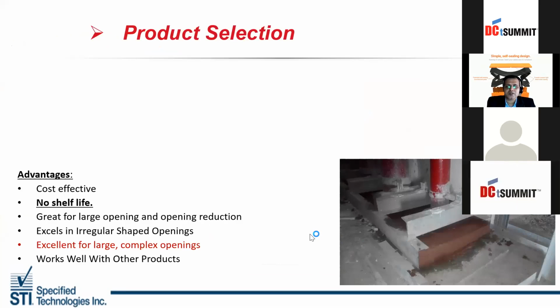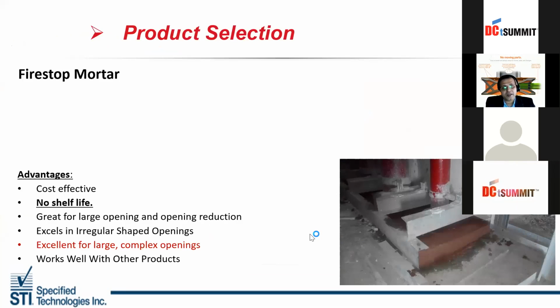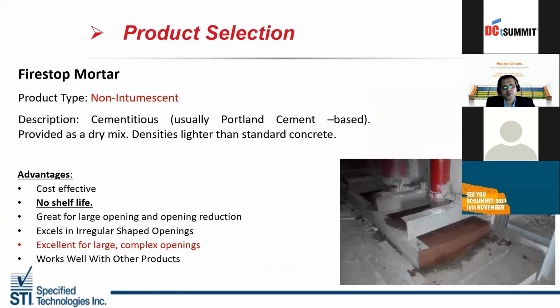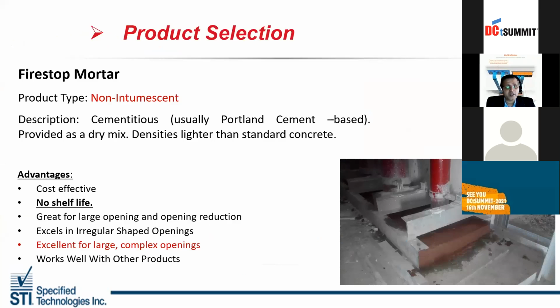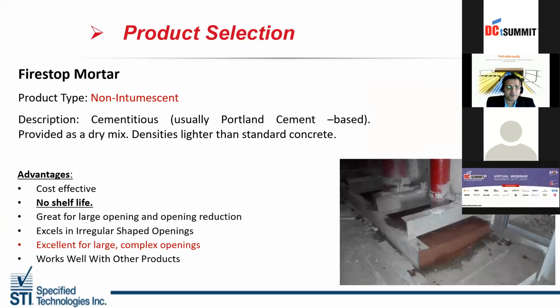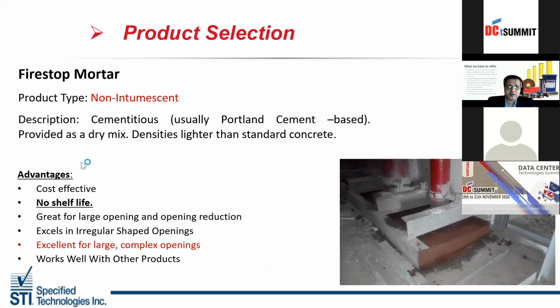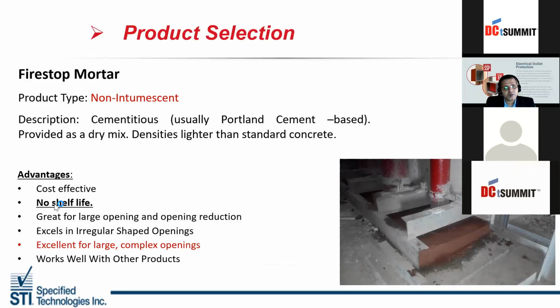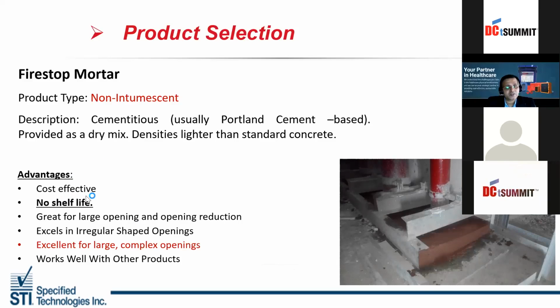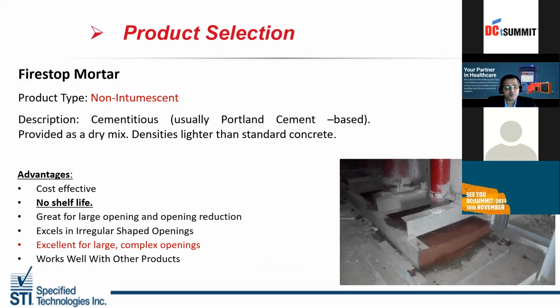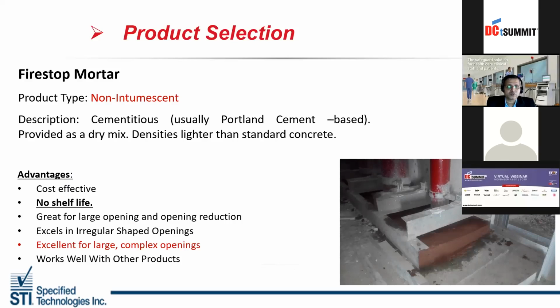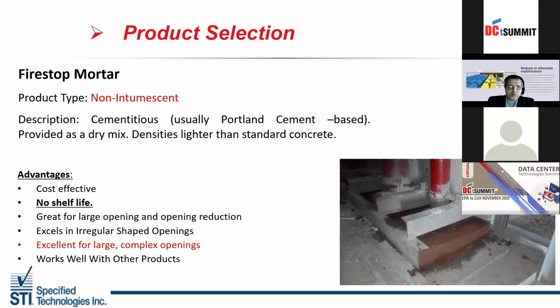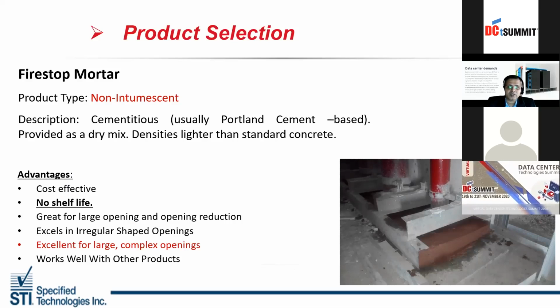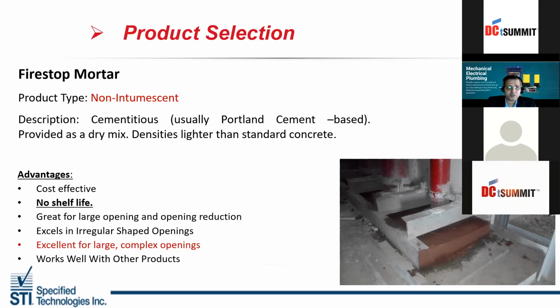Mortar, as I mentioned, is normally used for larger shafts where you have multiple penetrations or metallic penetrations, such as firefighting pipes and metallic ducts passing through a floor or a wall. Now coming to shelf life, normally all the sealants have a shelf life. The product we are offering doesn't have a shelf life. So suppose your project gets delayed and you have the mortar in your warehouse, no need to worry, because the mortar doesn't have a shelf life. It can be used after 6 months also.